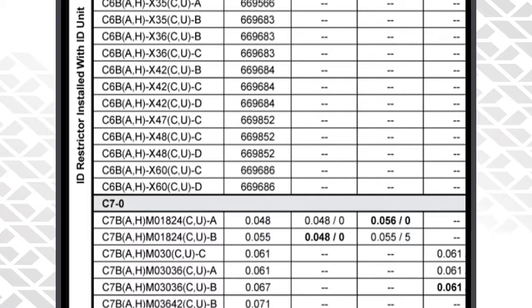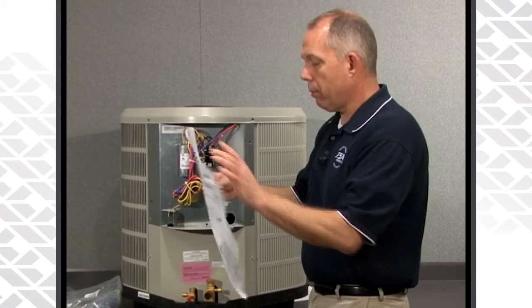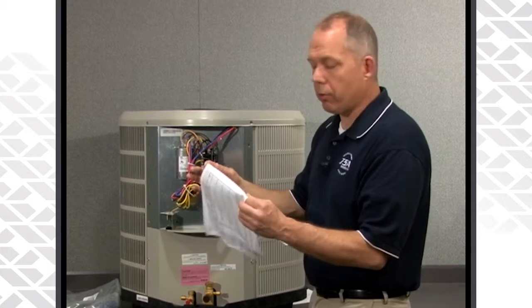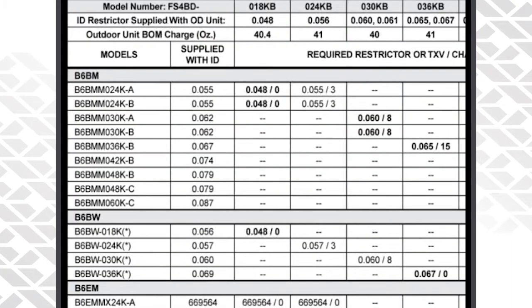As a quick example: we have a three-ton outdoor unit. If we're matching it up with a three-ton B6 air handler, we'll look under the three-ton column, match it up with the three-ton air handler, and we will need to change the indoor piston to a 65, and we will have to add an additional 15 ounces for a 15-foot line set.